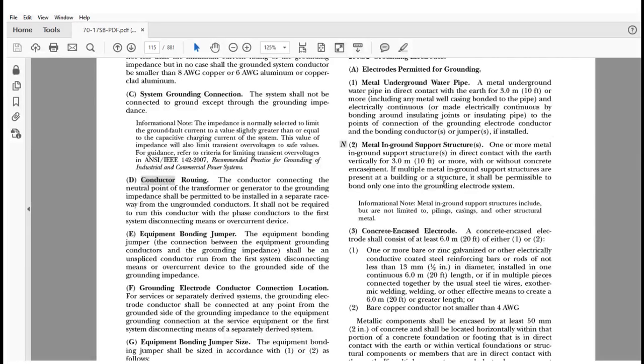Now, typically a metal frame of a building is usually above the ground, right? It comes to the pad, and in the past it could be connected with some J-bolts or whatnot to possibly a concrete encased electrode, which we have down here, and it makes the connection. This right here is talking about the metal of the building, the in-ground supporting structure. So that is your change here for the 2017 code. Now, it does say multiple metal in-ground support structures. Don't confuse this with the concrete encased electrode. This is an in-ground supporting structure, like a piling or a post that's driven or cored down in order to provide support for the structure, and it is in direct contact with the earth, and it is metal.